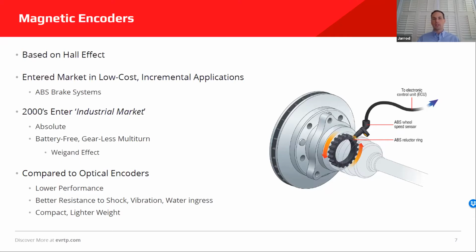And at that point, the potential energy is released, and it's great enough to power the EEPROM to do two very important things. One is note the fact that a rotation occurred. And second, it can note the direction. So it knows, should it count up or down? And what's so cool about the Wiegand effect is it does all this independent of speed. So it's not like a dyno where the light would get brighter if you pedaled faster. It's completely independent. So you could have a rotation that's slow or fast, and it can count.